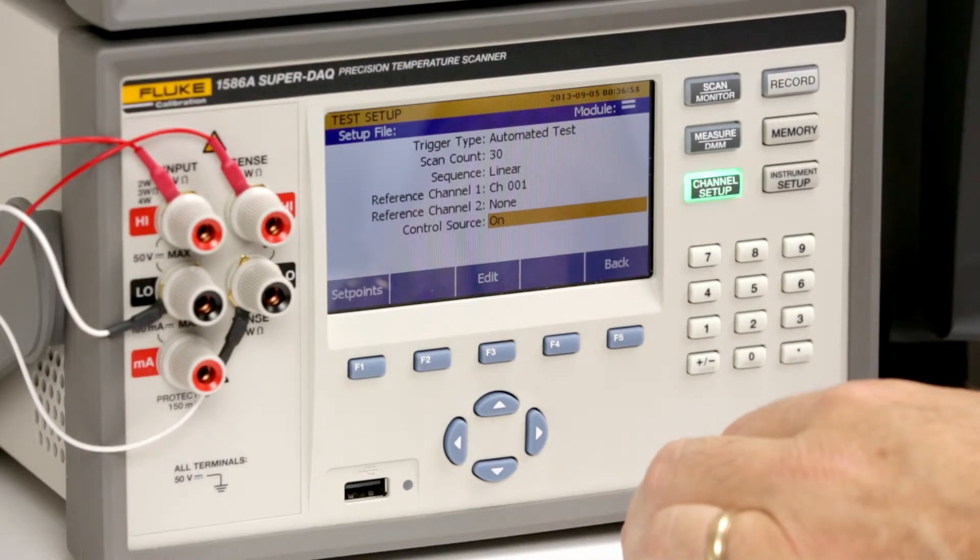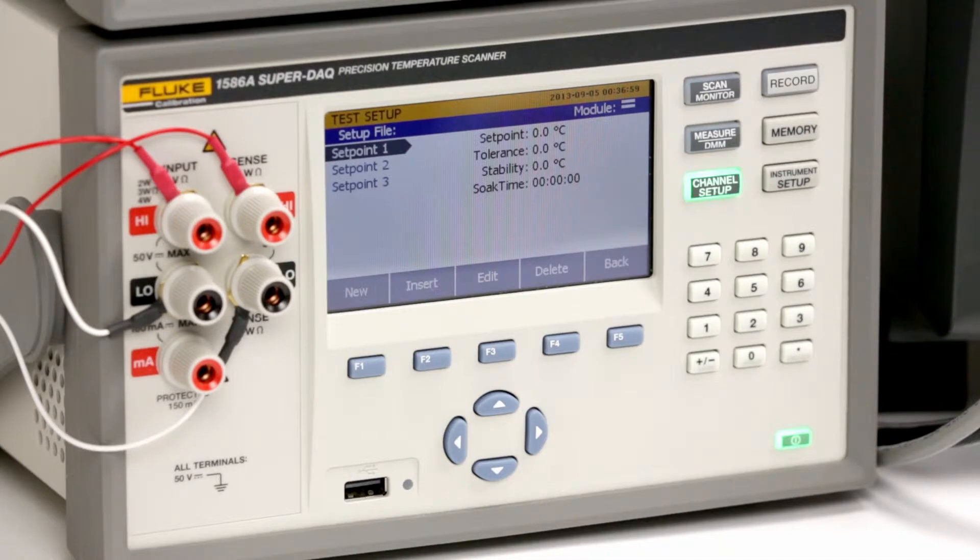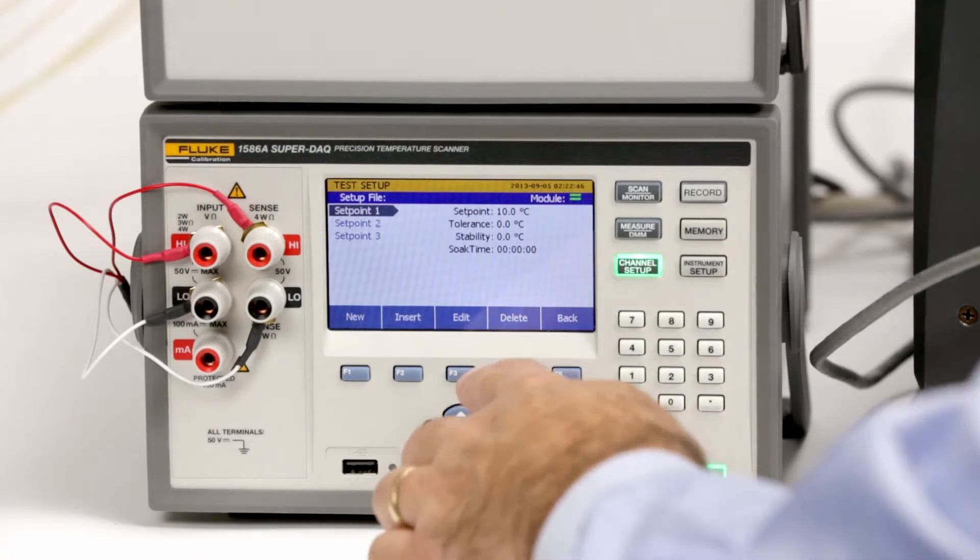Once configured, press set points. For this demonstration we are using a Fluke 9142 Field Metrology Dry Well. We'll use three set points for our tests.